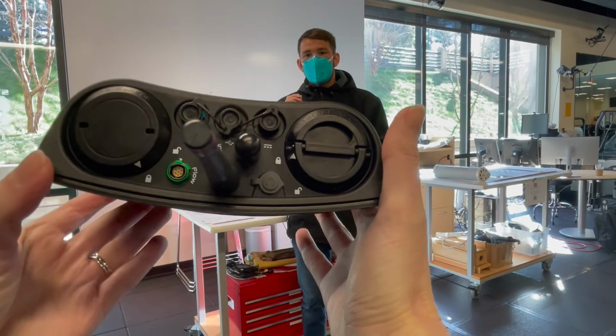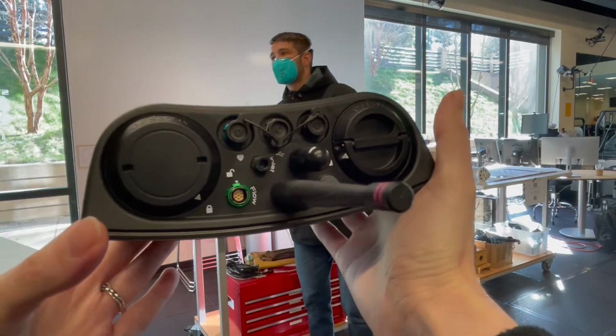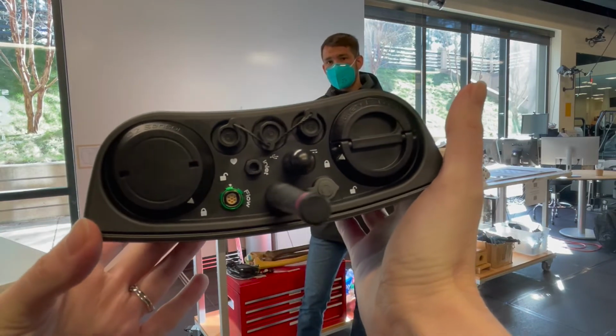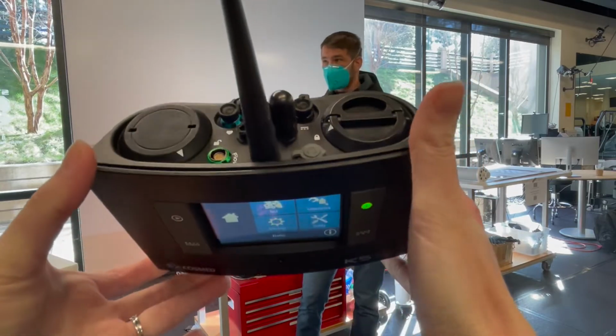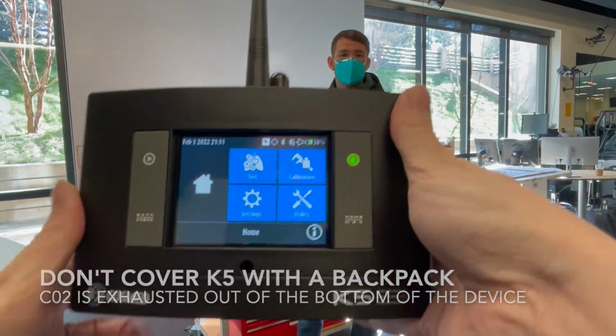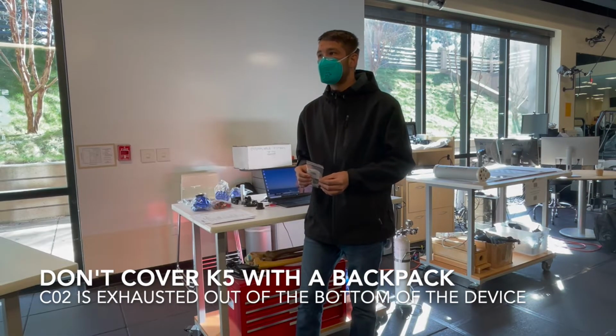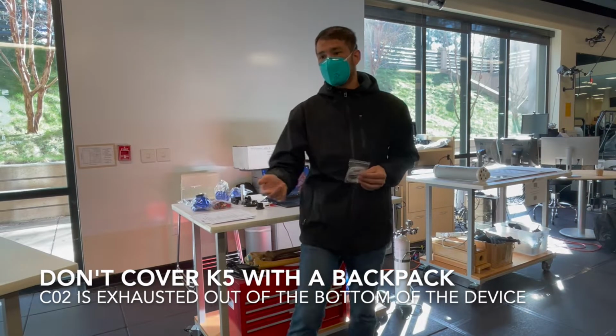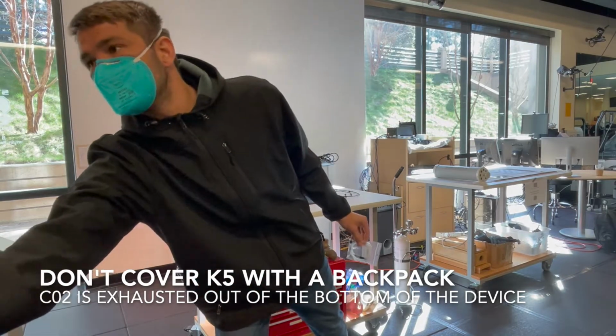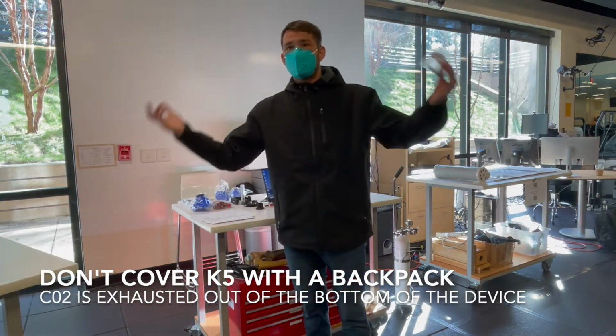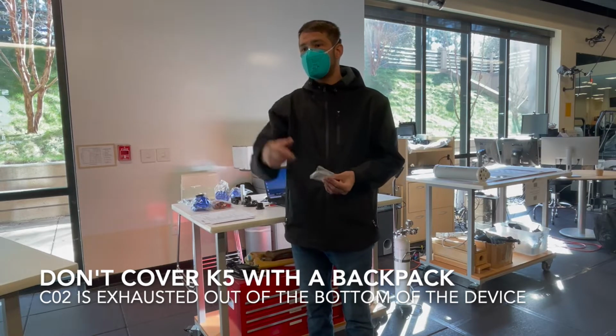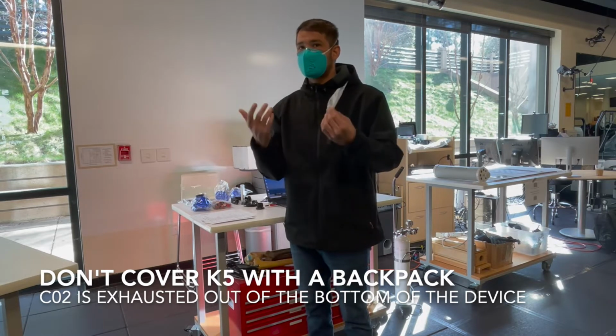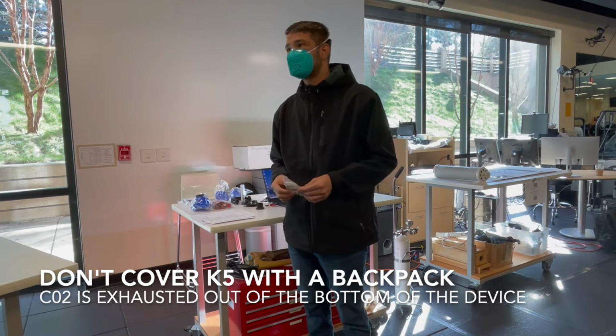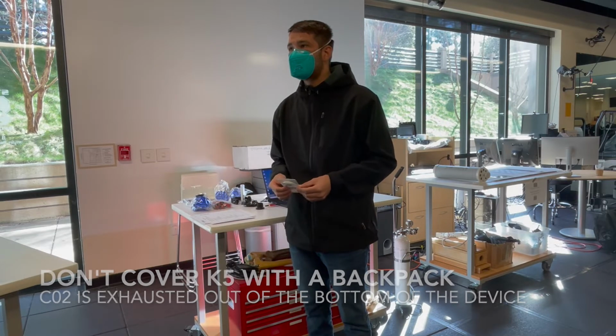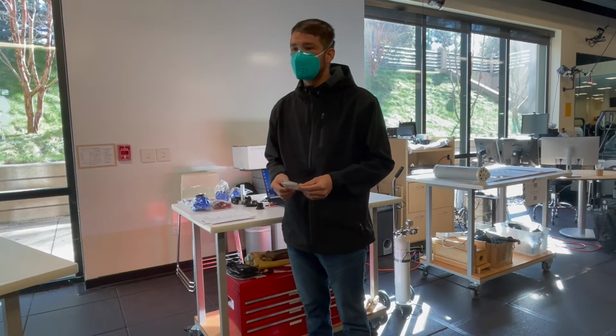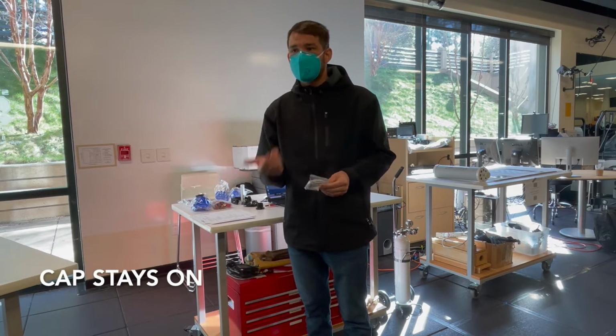It doesn't get very humid. Yeah, I was gonna say, so that's not really a problem, but if it is drizzling outside, the system is splash resistant. Don't try to cover it with a backpack or anything like that, because CO2 exhausts out of the bottom. So if it's in a backpack, it's gonna fill that little backpack up with CO2, and when it samples out of the FiO2 circuit, it's gonna be drawing in a bunch of CO2, and it's gonna throw off your system count. So then does this cap stay on during the test? The cap stays on, yeah, and it just draws air from underneath. Okay.